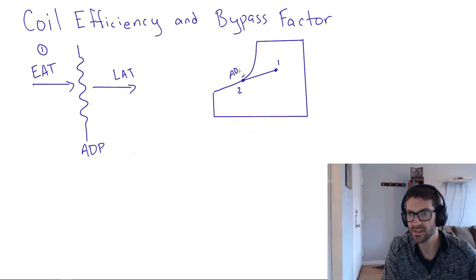It's idealistic to think that that would be our leaving air temperature. If the coil is 100% efficient, it will be. But if the coil is less than 100% efficient, then we won't quite get all the way down to point two. We'll end up somewhere close to two, but not all the way there. So maybe if it was an 80% efficient coil, we'd end up somewhere around here.